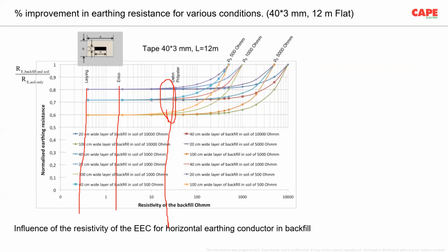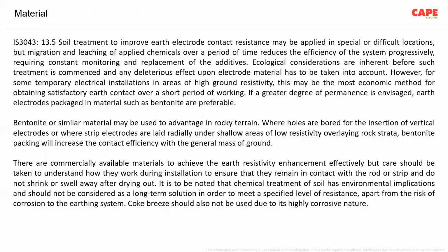So again, this study report shows that the resistance of the earth enhancing materials is immaterial in improving the resistance. Now, IS 3043, point number 13.5, talks about how to make the soil treatments, what are the advantages, what are the disadvantages. The final line you can see here: coke breeze should also not be used due to its highly corrosive nature. If you use coke breeze, of course, it will accelerate the corrosion.